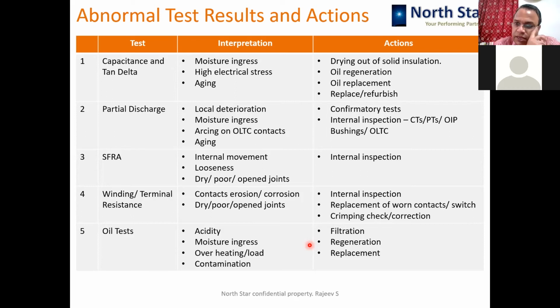SFRA test is basically a confirmatory test, especially in the large power transformers when the transformer is traveling from the factory to the site. It is possible that there could be some movement of the insulation blocks or some other components of the winding. This transformer will pass all the commissioning tests, but it may fail when the charging is done. So to prevent that possibility, the SFRA test is repeated and compared with the factory report, the test which is done in the factory. And if both the signatures are matching, then the transformer is taken for commissioning, else the internal inspection is necessary to be performed.